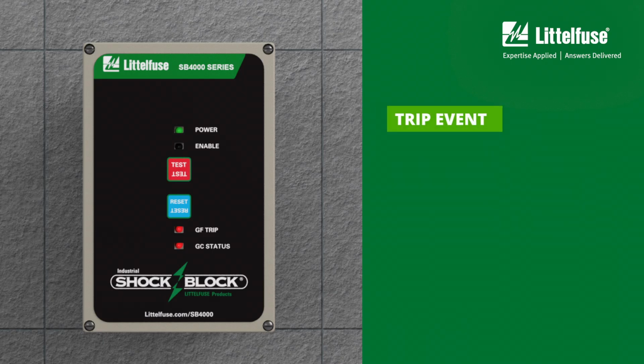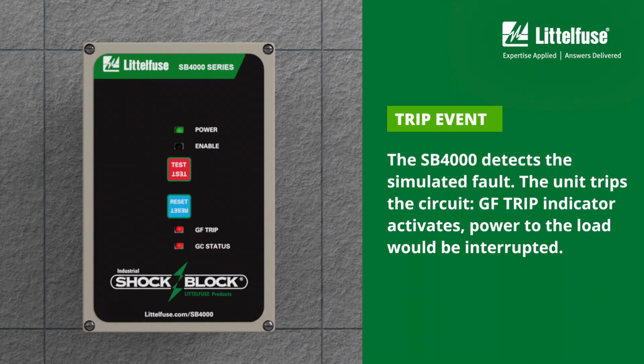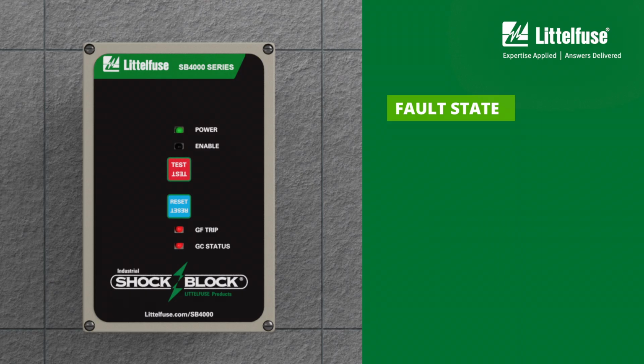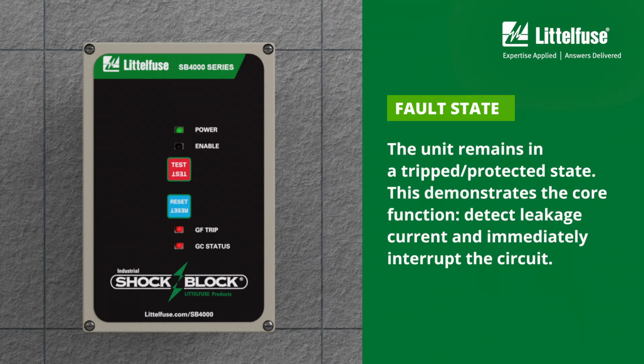Trip event. The SB4000 detects the simulated fault. The unit trips the circuit. GF trip indicator activates, power to the load would be interrupted. Fault state. The unit remains in a tripped/protected state. This demonstrates the core function: detect leakage current and immediately interrupt the circuit.